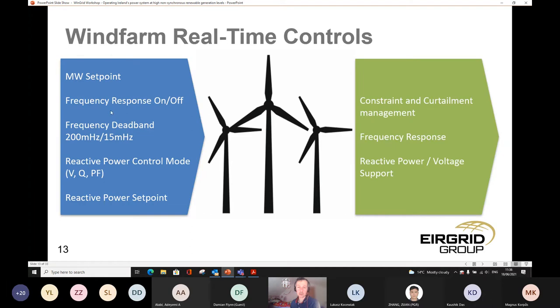With frequency response, we get frequency response from the wind turbines. We enable this tighter dead band, this 15 millihertz dead band at times, to be able to get enough frequency response on the system, especially during high levels of wind on the system when we're operating with not much conventional generation left, and traditionally the conventional generation has provided our frequency response. So as we lose that capability, the wind farms can essentially replace that and provide an element of frequency response.